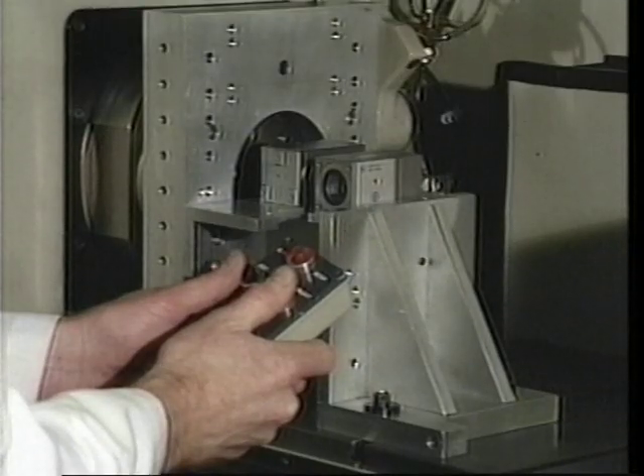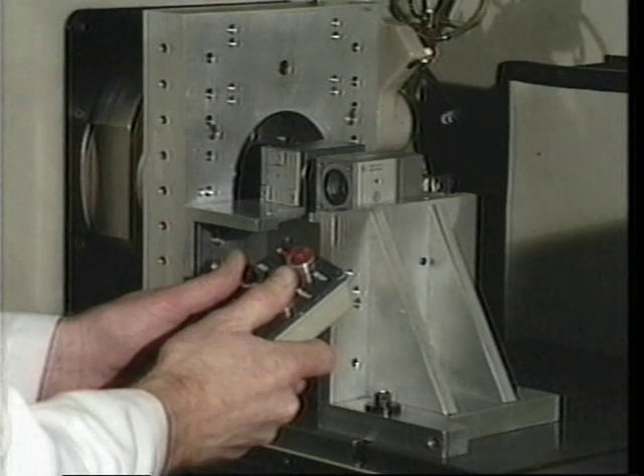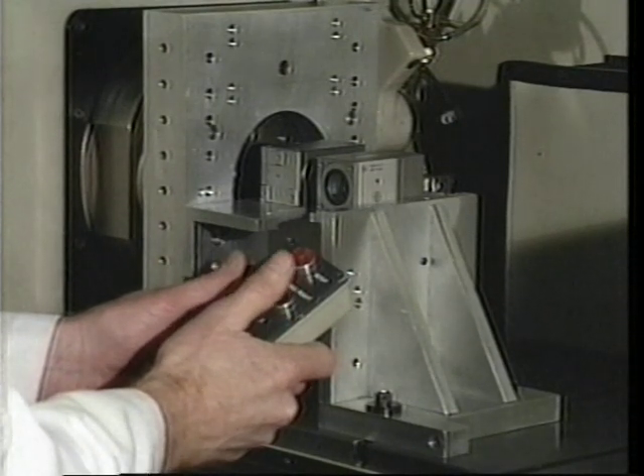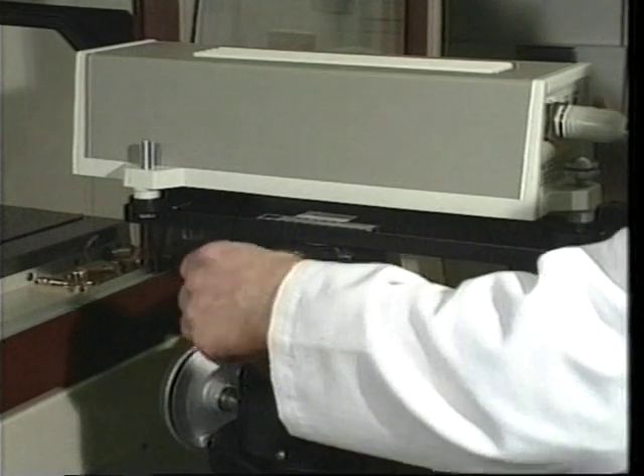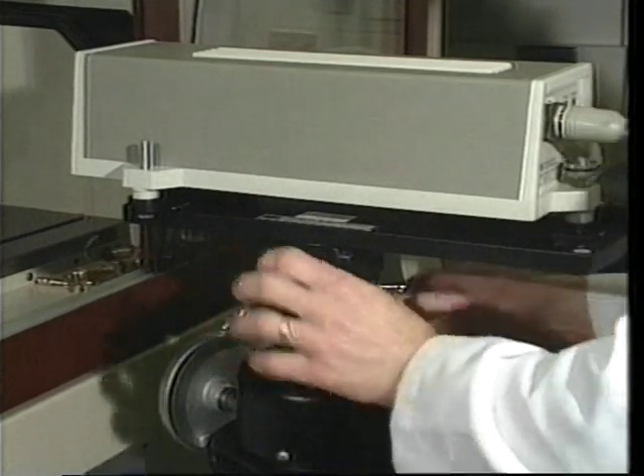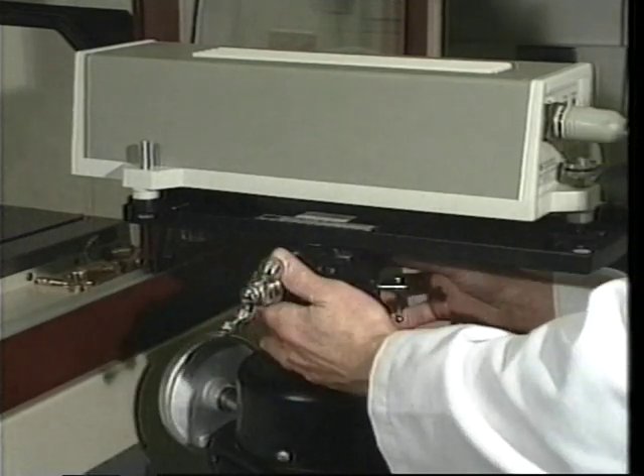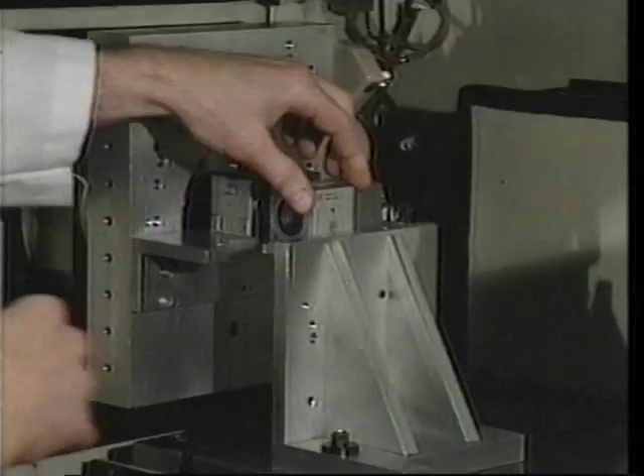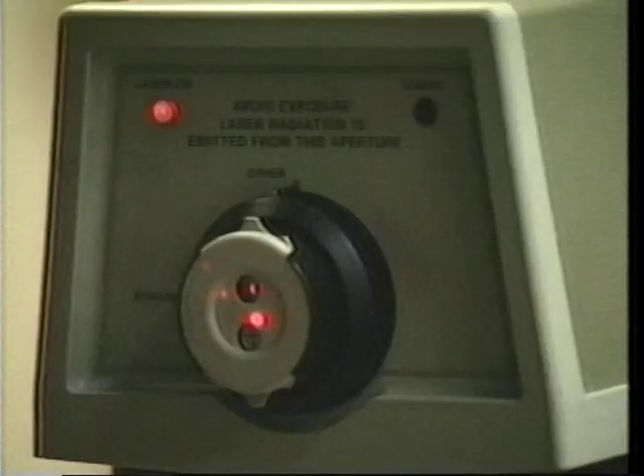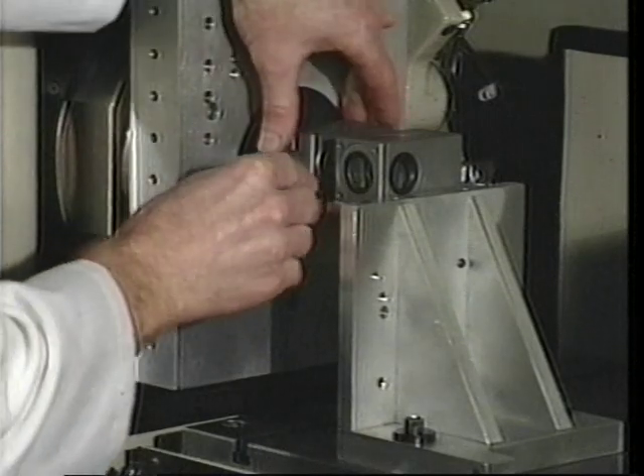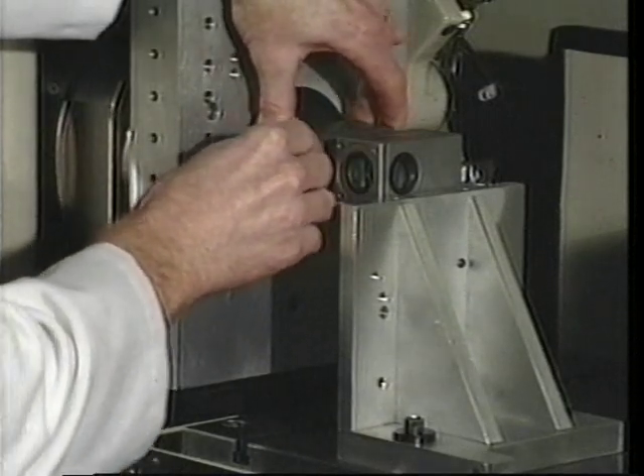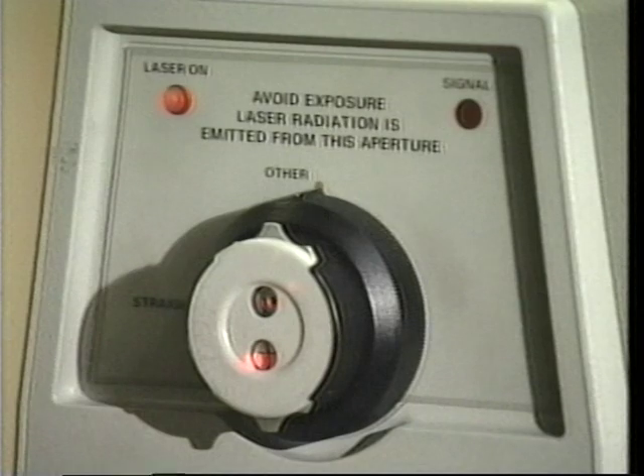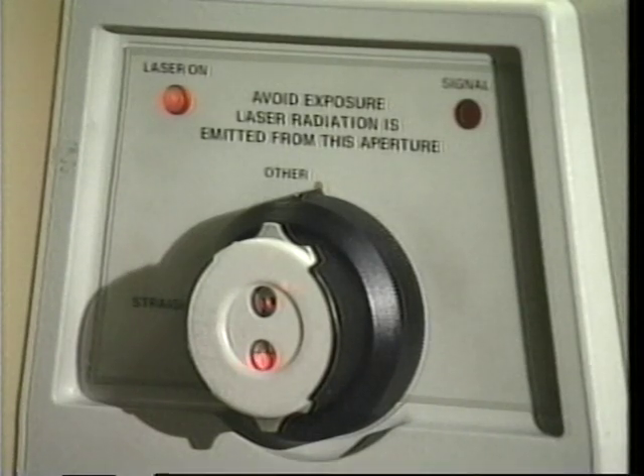This adjustment can be made by adjusting the position of the x-axis slide on which the interferometer rests, or by adjusting the position of the laser head using the tripod's angular and translational adjustments. Remove the target from the interferometer and note the position of the returning laser beam with respect to the return port on the bottom of the laser head. The position of the reflector must be adjusted until the returning laser beam is centered on the return port's crosshairs. This is referred to as establishing the near end of travel.